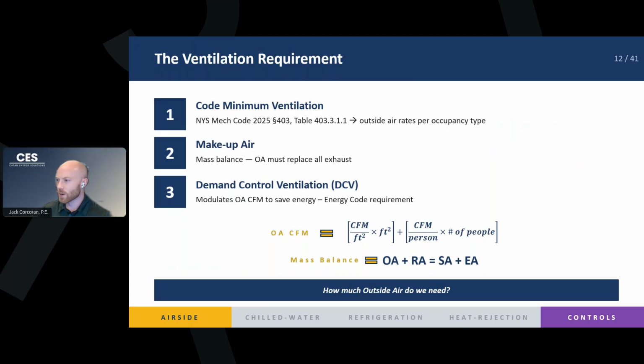So in addition to the minimum set by a code, right? If we have a lot of exhaust air in our space, you're going to also need a lot of outside air. Our mass balance equation is at the bottom, right? You need to sum up the air going in and the air going out, and they should equal each other as long as your pressure is the same, right? Or at equal pressure. So if you have a system that requires a significant amount of exhaust, you need to make sure you provide outside air into the space so your balloon doesn't deflate with all the exhaust going out. You need to make sure you're pumping in as much air as you're exhausting. So that also is a factor in what determines the CFM of our outside air.